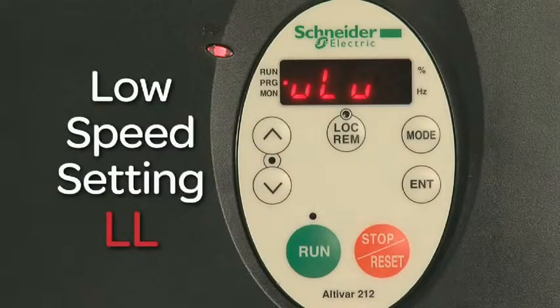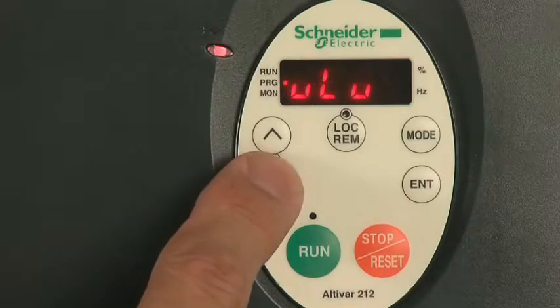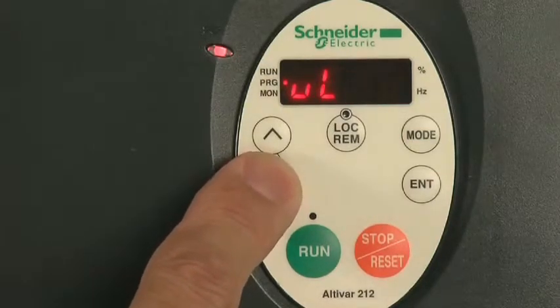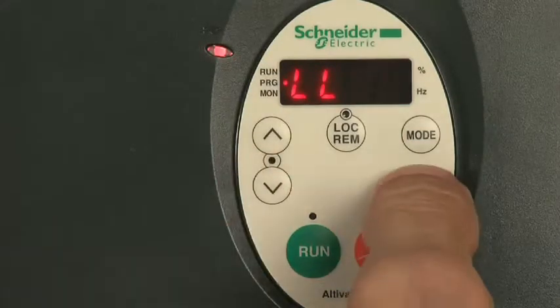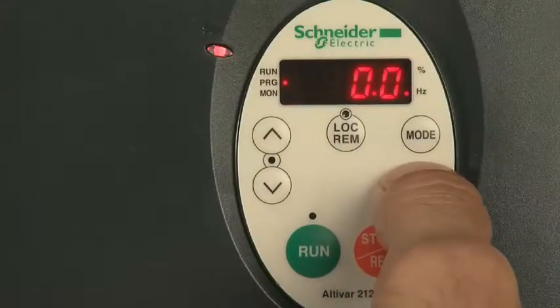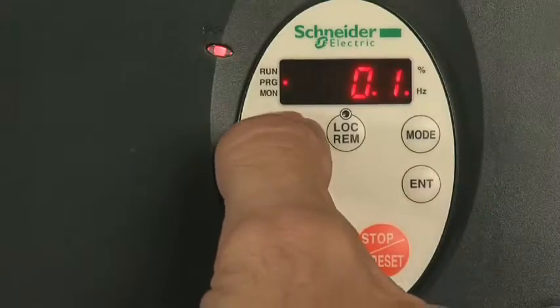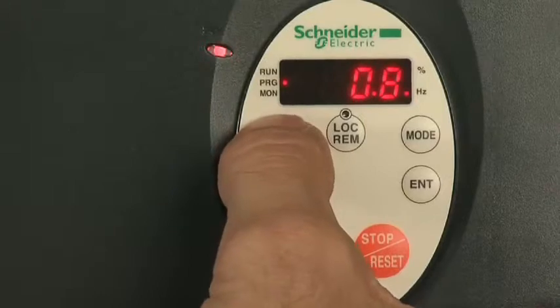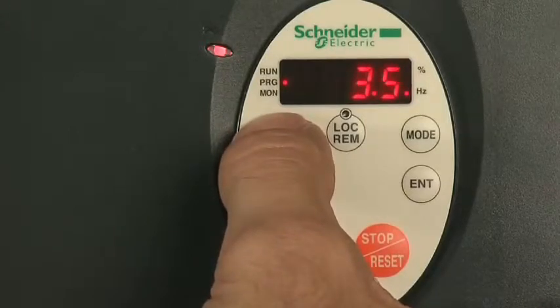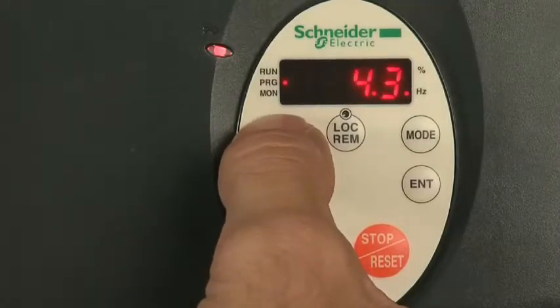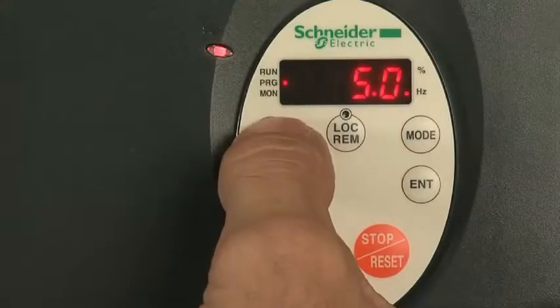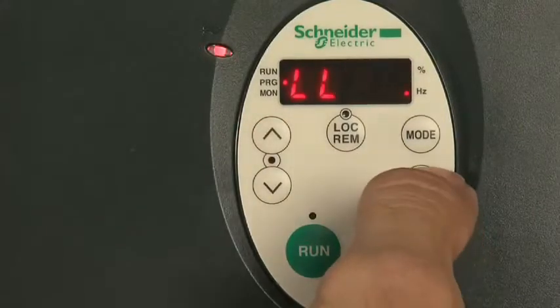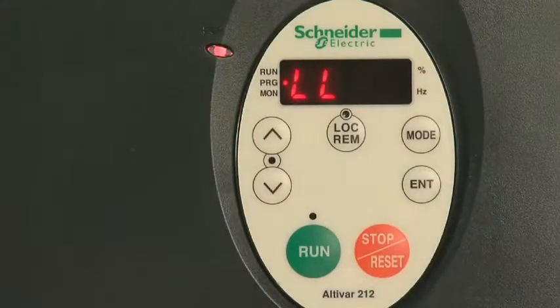Next, we will configure the low speed setting, labeled LL. Navigate down to LL. Press ENT. The factory setting for this device is 0 Hz. The recommendation is to set this value to 5 or 10 Hz so that a run command will cause the motor to rotate at a minimum speed. You can set this to another value for your application.